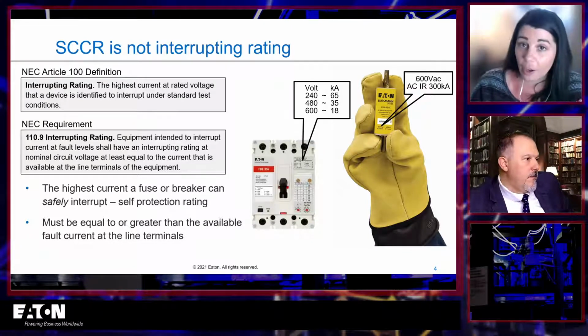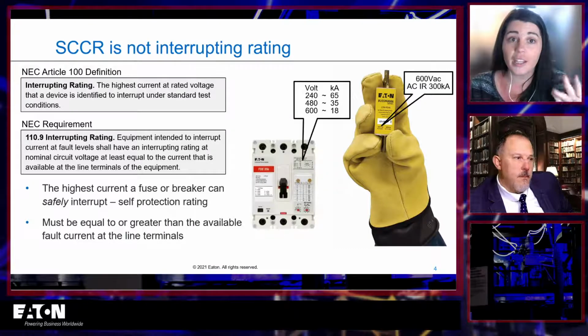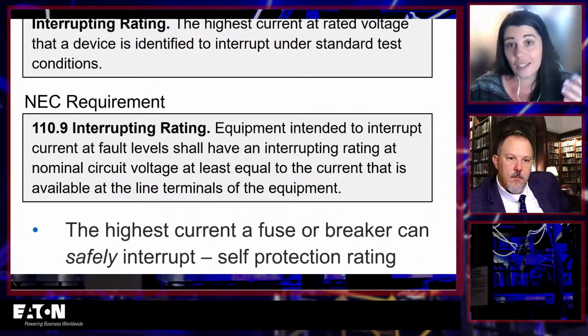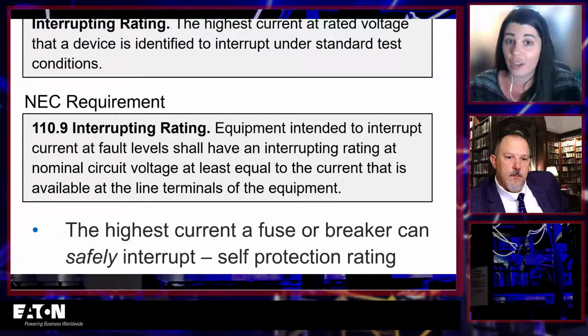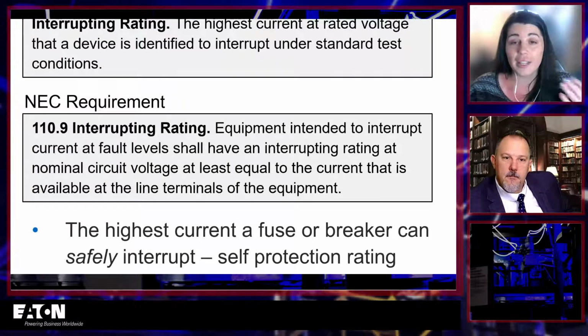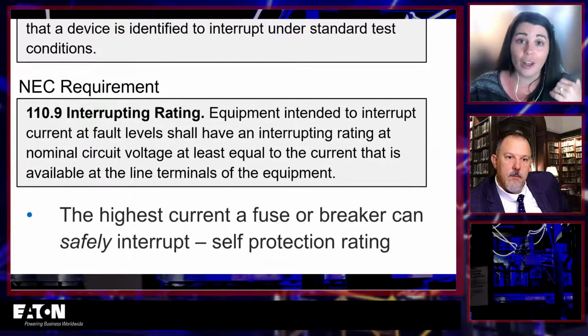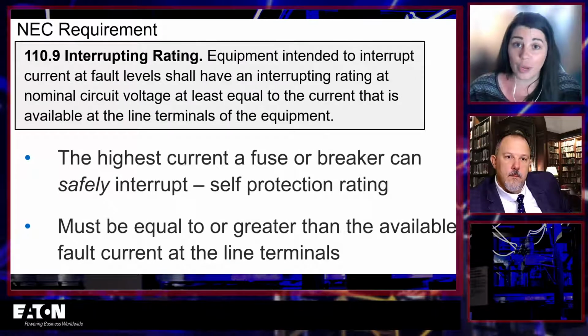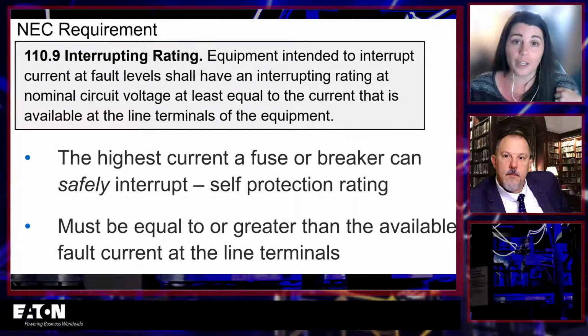There's an NEC requirement about interrupting ratings. 110.9 is essentially going to say all my interrupting ratings should be greater than or equal to the available fault current. That makes sense. It's just like something like a voltage rating. You want your voltage rating to be greater than or equal to the voltage of your system. You want your interrupting rating to be greater than or equal to the available fault current.